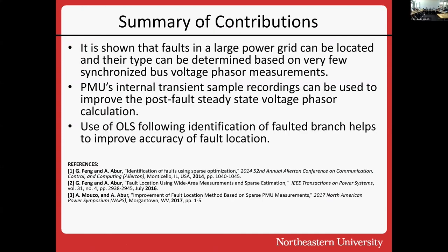I guess with that, I would like to conclude, this is a way to locate faults if you have a limited number of synchronized voltage phasor measurements in a given power grid. You can improve this by using some sort of a prediction algorithm based on something like Prony to take the transient sample recordings and determining the post-fault steady state values that way, because those are not going to be captured by PMU since the relays are not going to allow you to keep the faults that long active and live in the system.